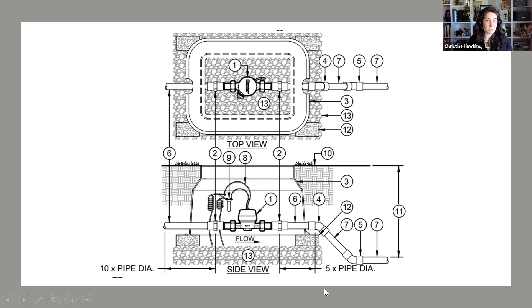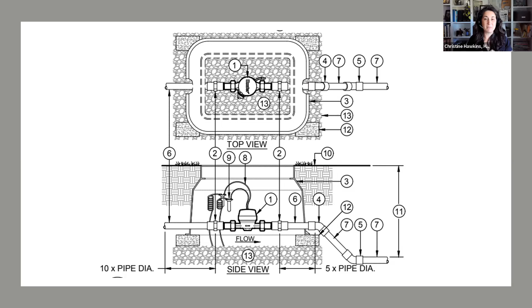So if this were a 1-inch sensor, we've decided based on our flow ranges, we need this to be a 1-inch sensor. You'd put 10 inches or 10 times that diameter upstream of the pipe without restrictions or fittings, and 5 inches or 5 times that diameter on the downstream side. You may have a main line that is larger. Maybe it's a 1.5 inch or a 2-inch main. That's fine. You'll need to size down just for this particular section. It's a very short section. You're not going to see a lot of pressure loss through that. There's no obstructions there, but it's very essential for clean data. Next slide.